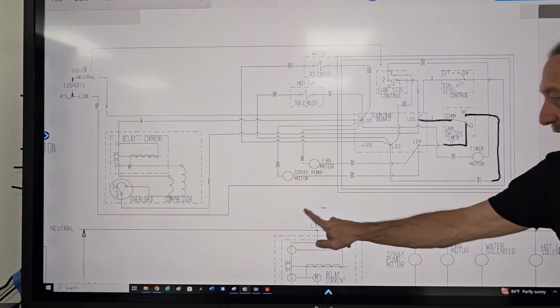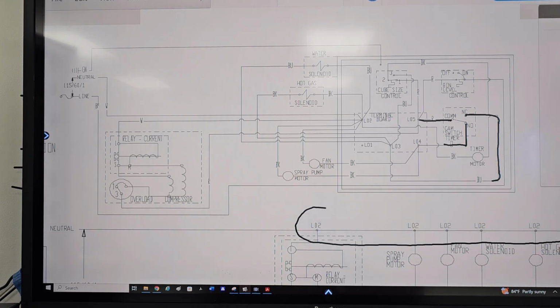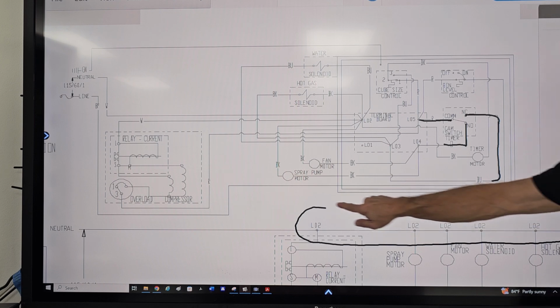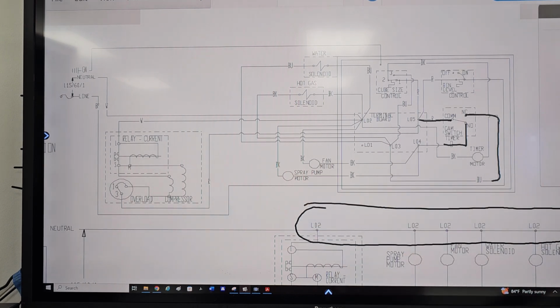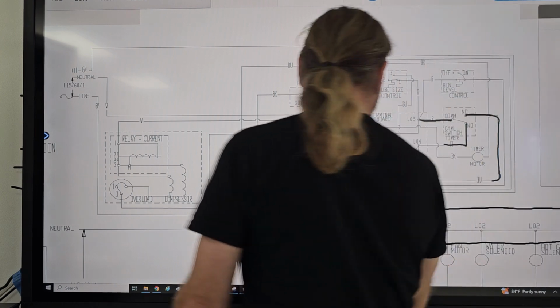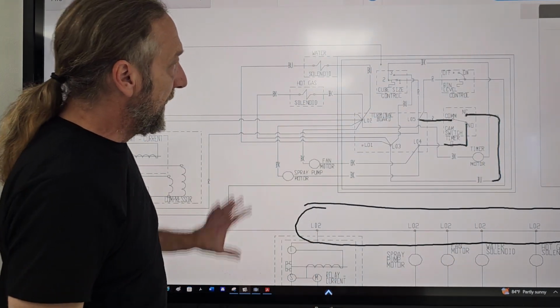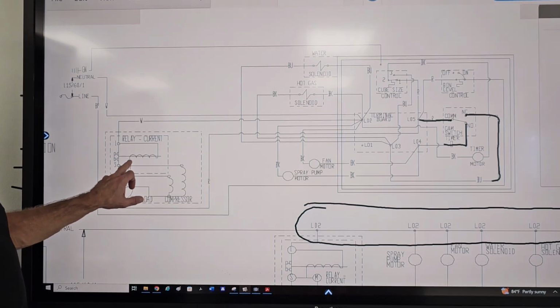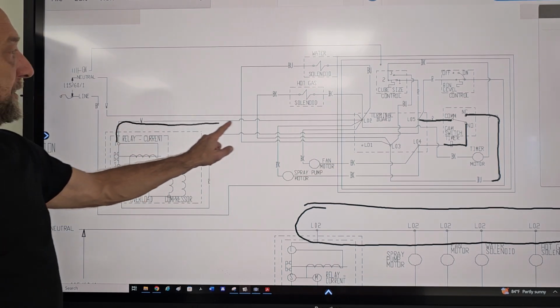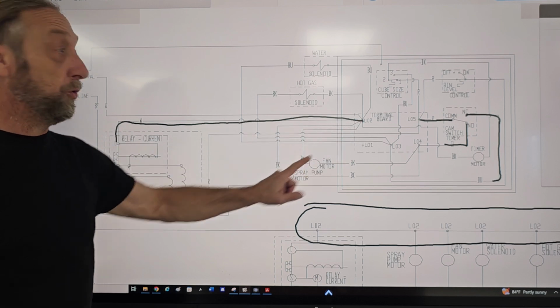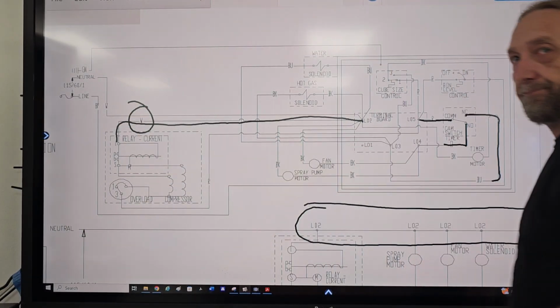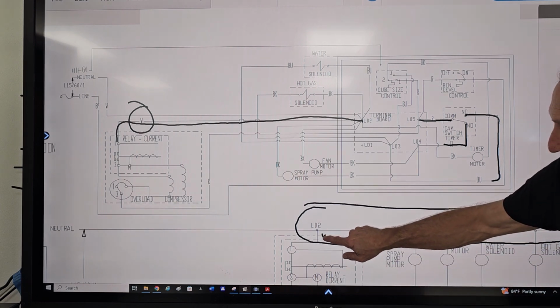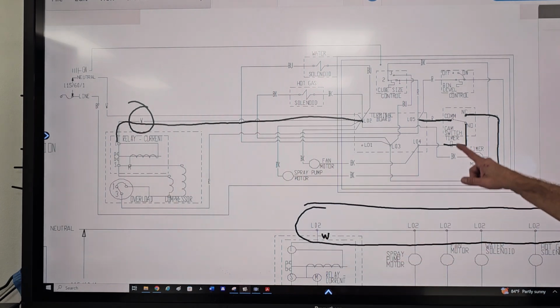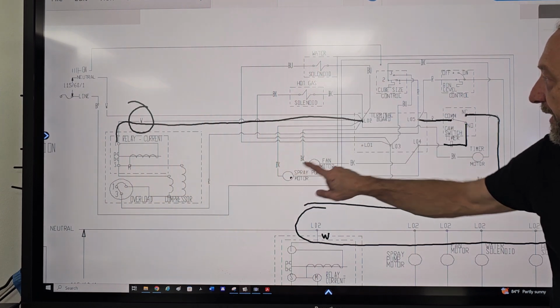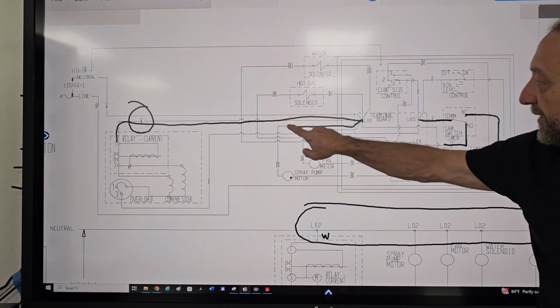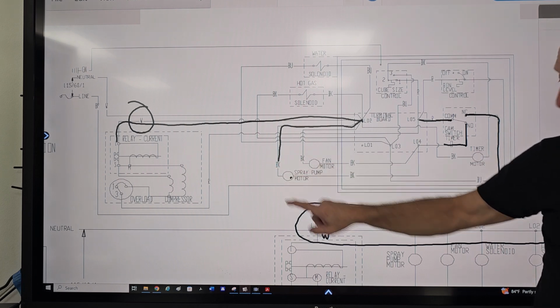If we look here, all these L02s go all the way over to my timer motor. Coming off the compressor, I follow this one and it goes to L02, and the wire color is white. So this one's white. The spray pump motor, where is it? Here, and L02 is here. That's a black wire, so this one's black.